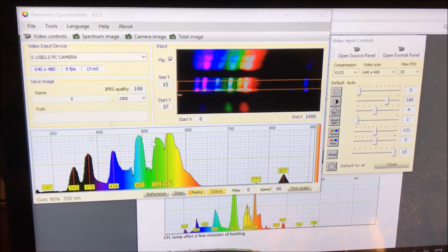All right, so that's not great, but hey, it's a quantitative result, and we can take a look here and try to match this pattern, since we got some peaks here, to the known compact fluorescent pattern. And this is in fact how you calibrate this instrument. You use the known emission peaks from a fluorescent bulb, and since those emission peaks are based on the emission of chemical elements, they're never going to change.